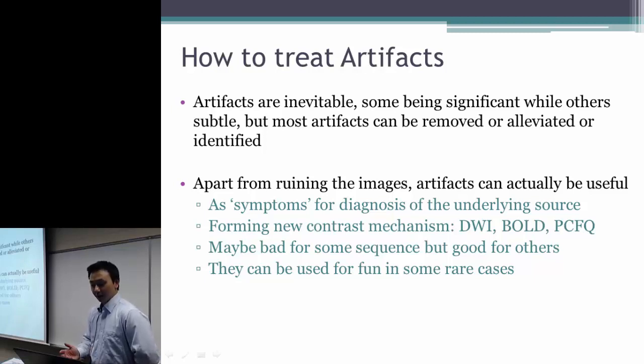Apart from ruining the images, the artifact itself can actually be very useful. When we see an artifact, we know that something is wrong. So the artifact itself can be used as a symptom of a disease, so that we can use it to diagnose the underlying source or problem, to see whether it is a problem from the hardware or a problem in the imaging parameters.